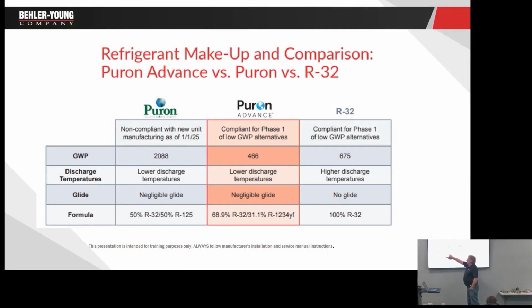So again, R410A is over 2,000 GWP, 454B is 466, R32 is 675. Now, why did the Daikin family go to R32? Who knows? But they did. So now, if I look at the composition, I don't want to get into this too in depth, but 50% of R410A is R32. 454B is 68% R32. So the point is, you've been working with R32 all this time. As long as you've been working with 410A, you've been working with R32. You just have a little heavier amount of it.